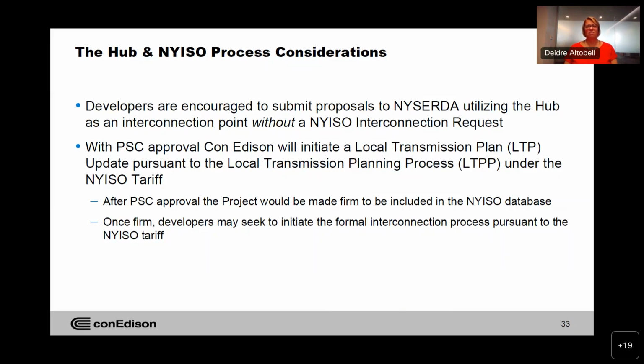So when can a developer select the Brooklyn Hub as its POI? Once Con Edison receives cost recovery approval from the Public Service Commission for the Brooklyn Clean Energy Hub, it will initiate an update to its local transmission plan. In that update, it will notify the NYISO that the Brooklyn Clean Energy Hub is a firm project with an expected in-service date of 2027, to be included in the NYISO database. Once the hub is included in the NYISO database, developers may seek to initiate the formal interconnection process, including selection of the hub as the offshore wind project's POI, pursuant to the NYISO tariff.